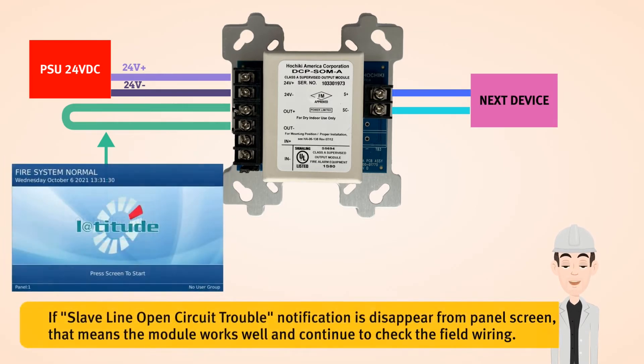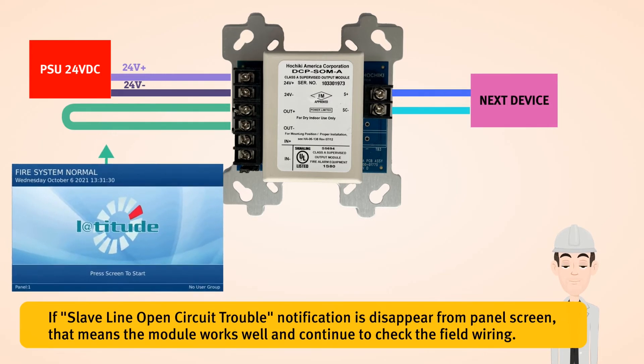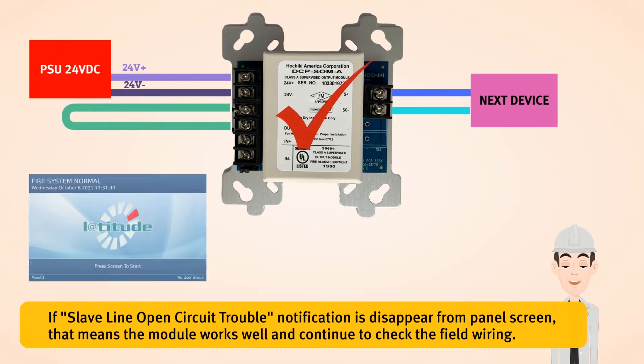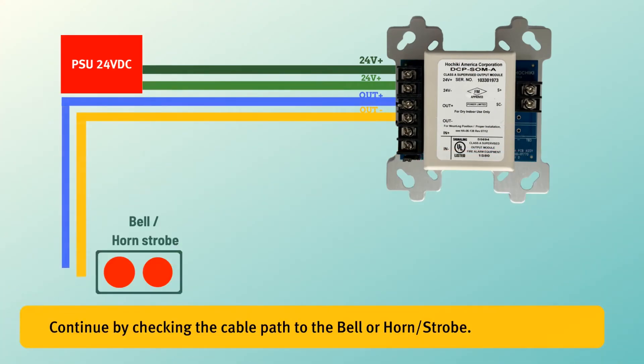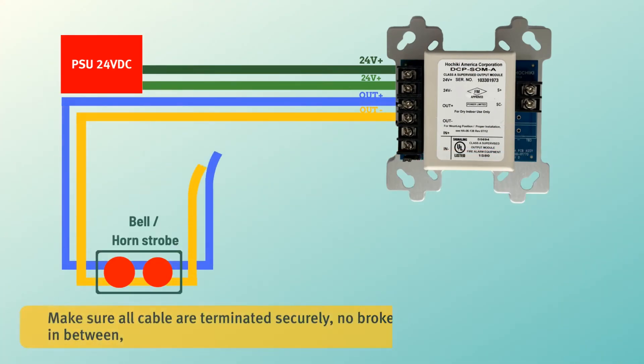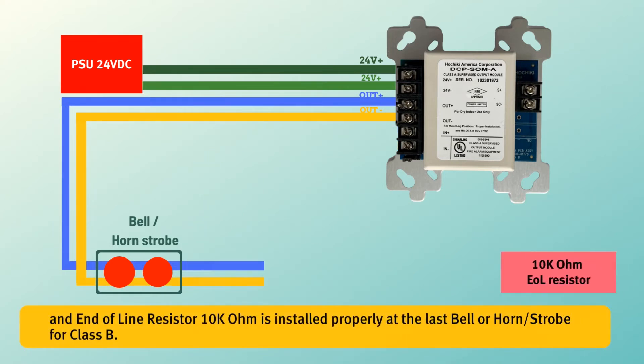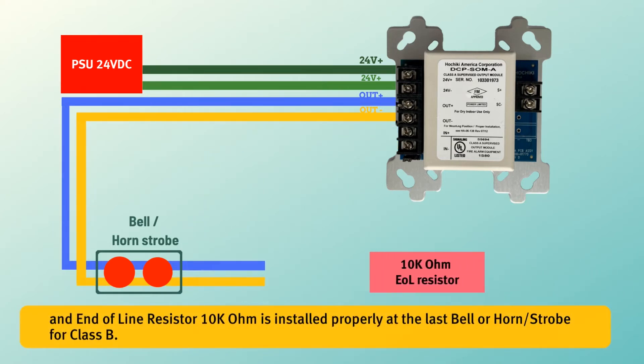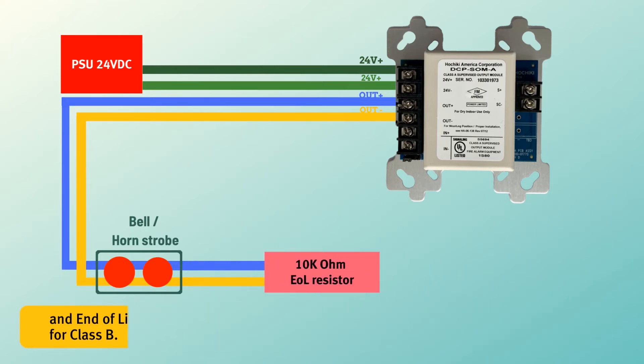If the slave line open circuit trouble notification disappears from the panel screen, that means the module works well — continue to check the field wiring. Check the cable path to the bell or horn strobe. Make sure all cables are terminated securely, with no broken or open cable in between. An end of line resistor of 10k ohm must be installed properly at the last bell or horn strobe for Class B.